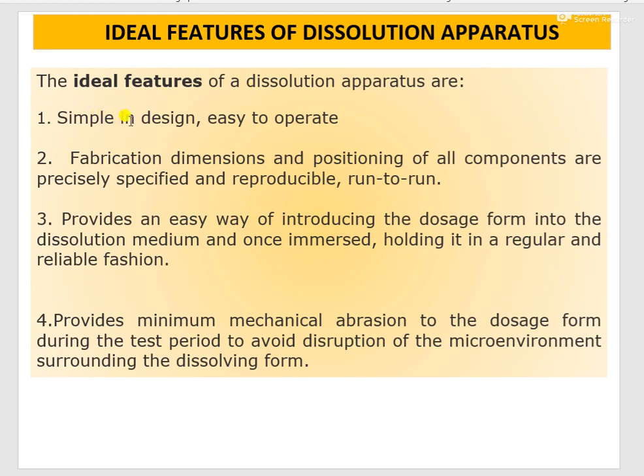Dissolution apparatus should be simple in design and easy to operate. Fabrication dimensions and positioning of all components should be precise and reproducible, and there should be run-to-run uniformity. It should provide an easy way of introduction of the dosage form into the dissolution medium, and once introduced or immersed, it should hold it in a regular and reliable fashion. There should be minimum mechanical abrasion to the dosage form during the test period to avoid disruption of the microenvironment surrounding the dissolving form.